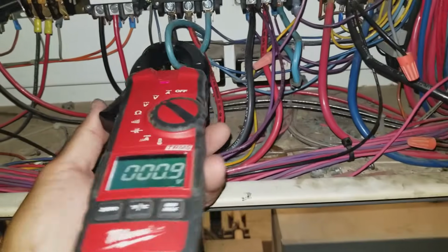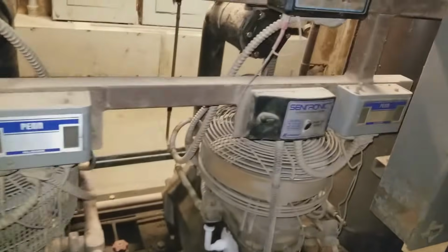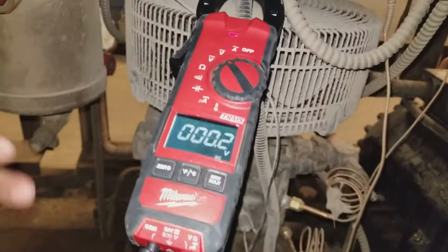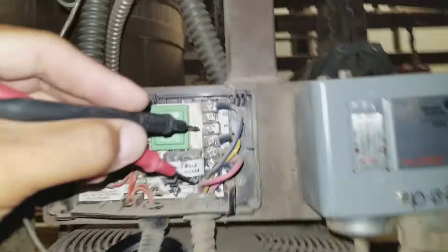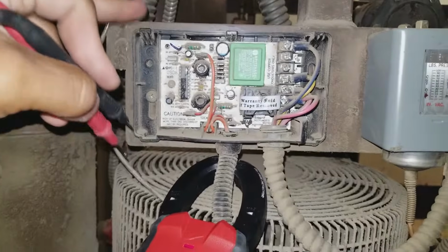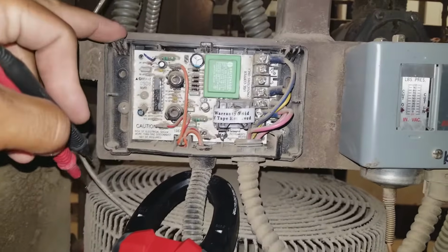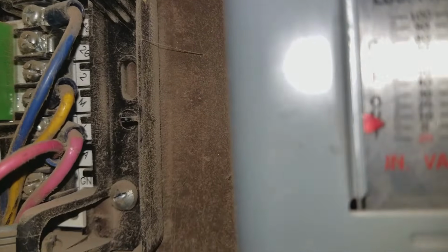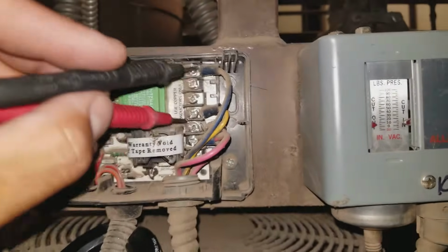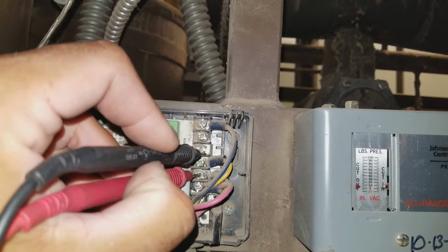So let's check out the safety. So here's my compressor 3. Compressor 1. So this is my oil fail right here. Of course the cover's missing. Over time that eventually happens. The little clips break and then they don't go back on properly. So I don't know if you can see in there, but it does say L and M. Those are my controls. So I'm going to put my leads up against L and M, so that's part of my control circuit.